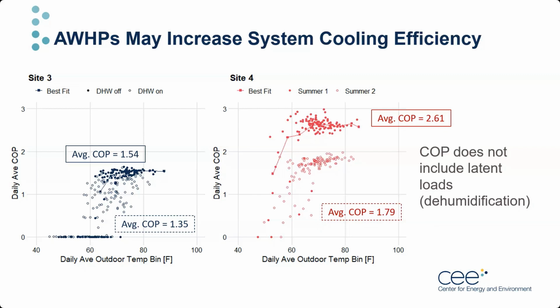Site 3's data are split into hollow points for when domestic hot water was enabled and filled points with no DHW capability on those days. A big takeaway from here is that the system having to switch between cooling mode and heating for DHW preheating has a clear cooling energy penalty, at least at the daily level.